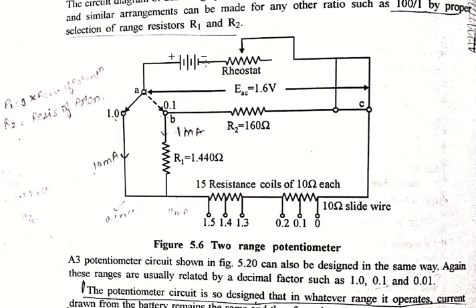The condition can be achieved only if the voltage EAC remains the same for both ranges of potentiometer, so that the current drawn from the battery remains same for both positions of the range selector switch. The current through resistor R2 should be equal to 1mA on range 1.0 and 10mA on range 0.1.